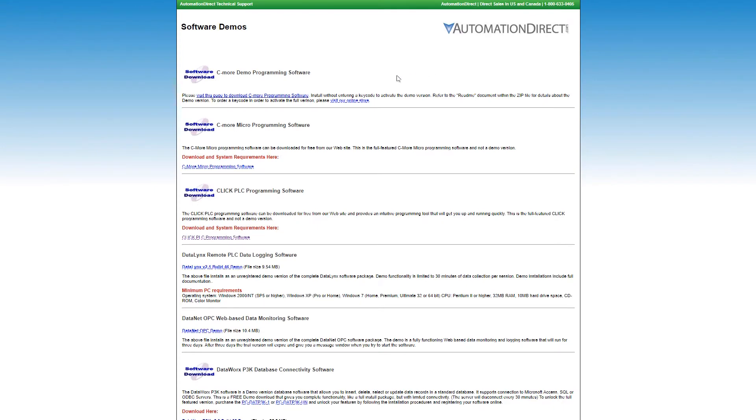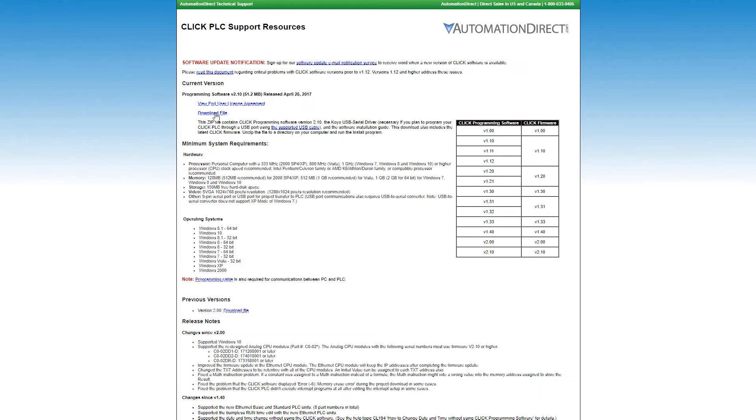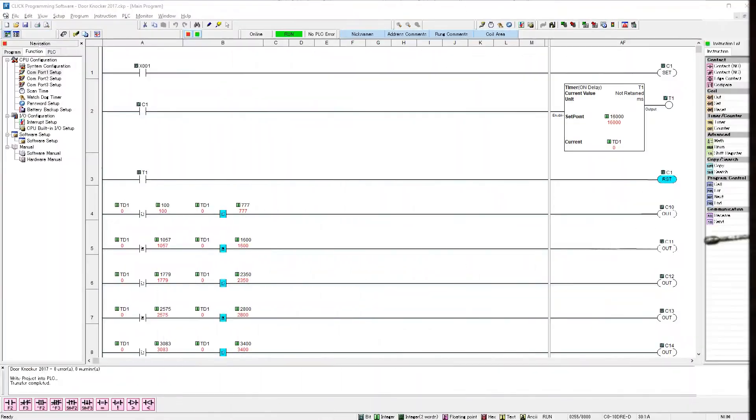Again, our Click PLC programming software can be downloaded for free from our AutomationDirect website. In this program I have the sensor on our X1 input. When it turns on I set an internal contact. This contact triggers timer T1 and when the timer equals some set values that I choose it turns on and off the outputs Y1 to Y5.